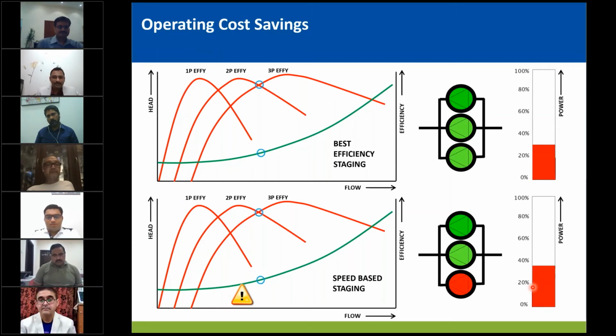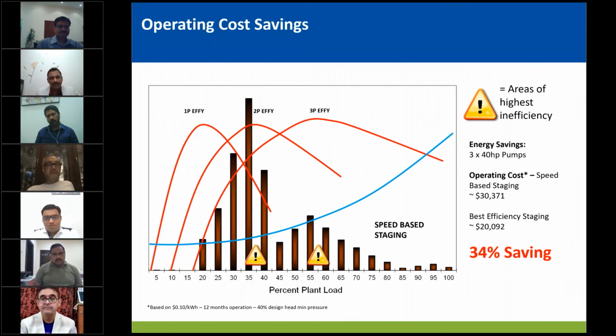Now, for the second pump to third pump transition, the same opportunity exists. And if you actually look at that operating point and put a load profile on the same curve, you will see you're spending most of the time at that point for this load profile, and this point as well. So if you put 3 into 40 HP pumps and a dollar value for that savings, it is coming up to 34% energy savings just by staging pumps in parallel and at best efficiency points.